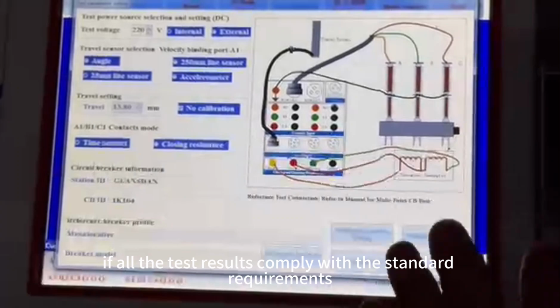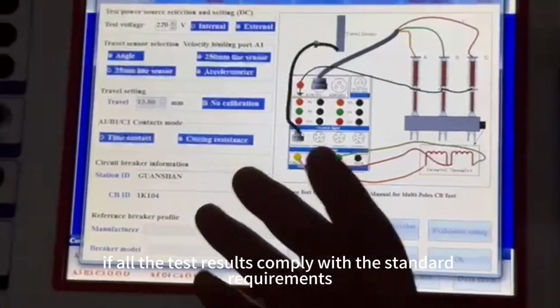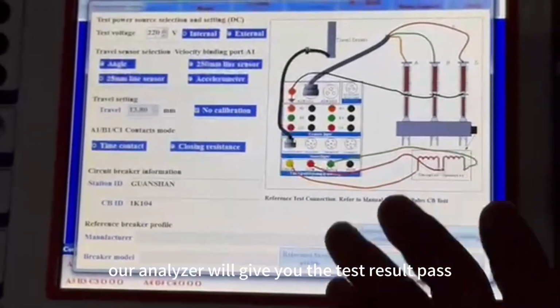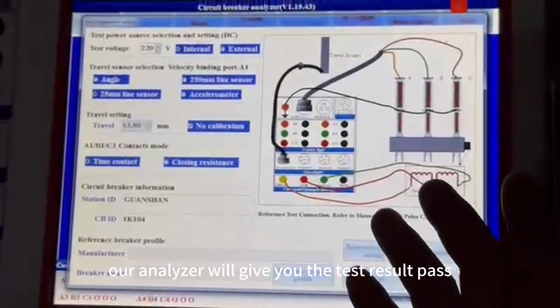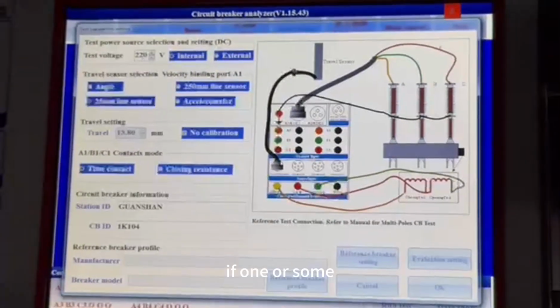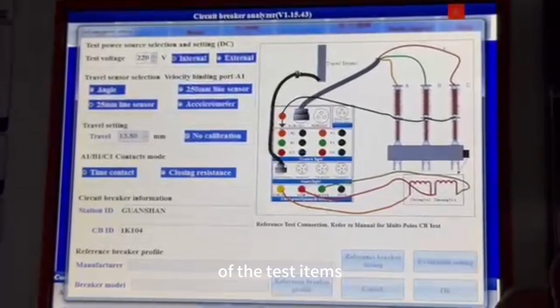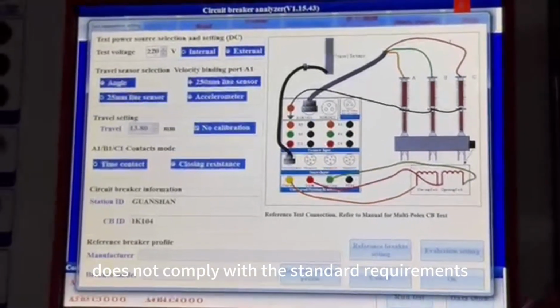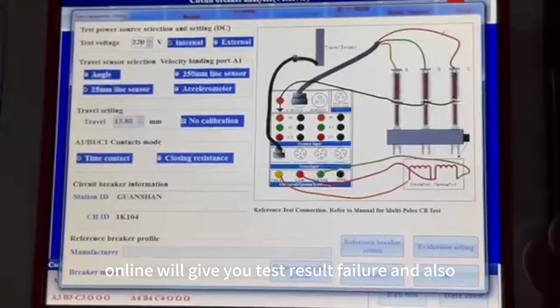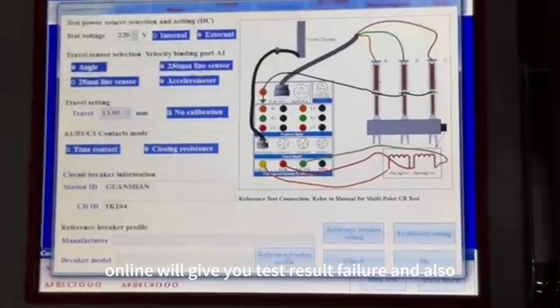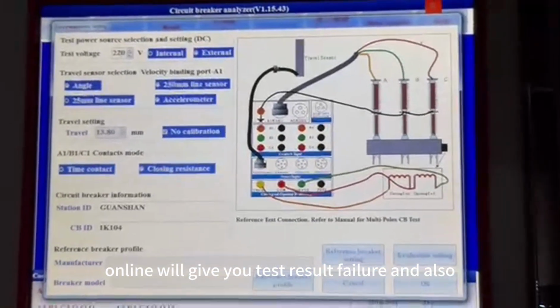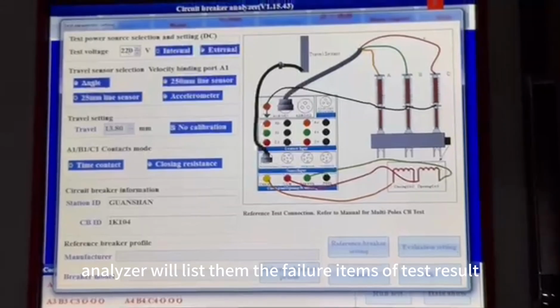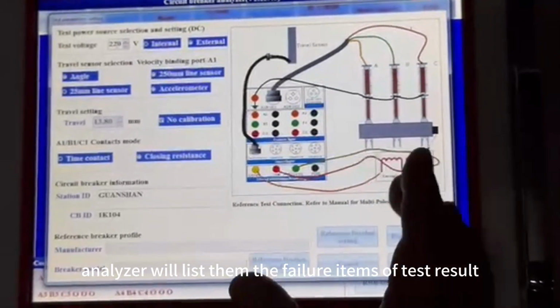If all the test results comply with the standard requirements, the analyzer will give you the test result pass. If one or some of the test items do not comply with the standard requirements, the analyzer will give you a test result failure, and the analyzer will also list the failing items of the test result.